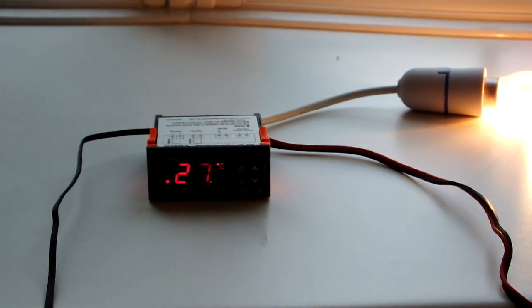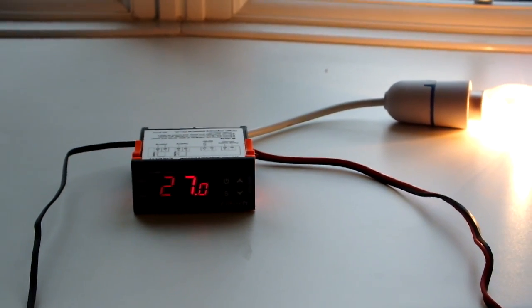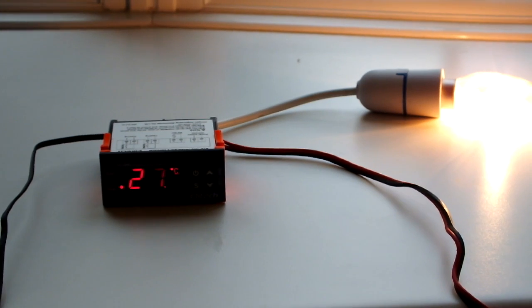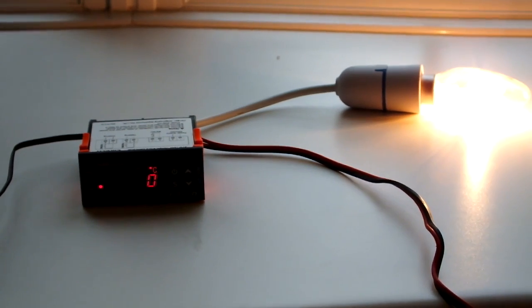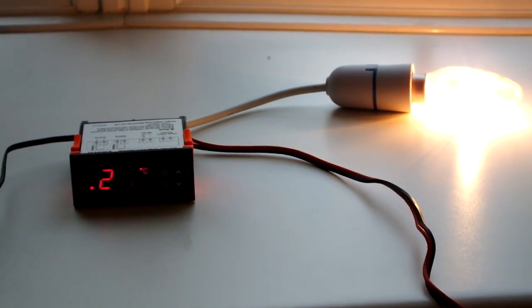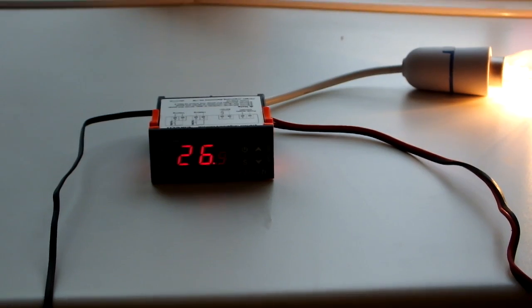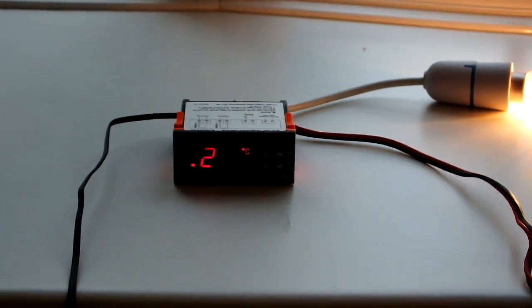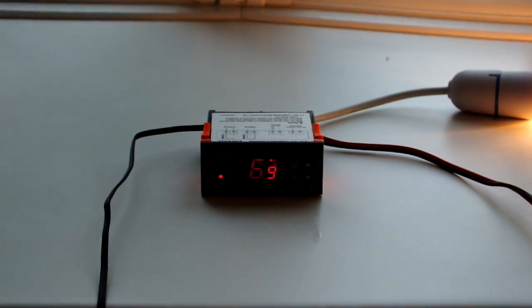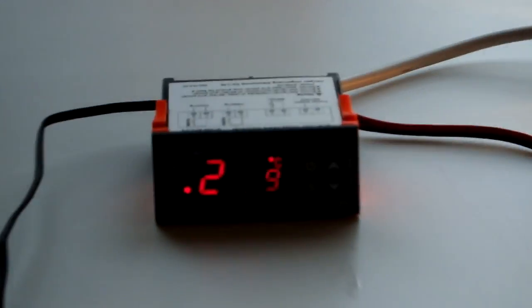Okay, so I've just wired up this Elitech STC1000. I'm using the light bulb to simulate the heater, and if you look at the display on the Elitech, it's reading 26.9 on the LED.